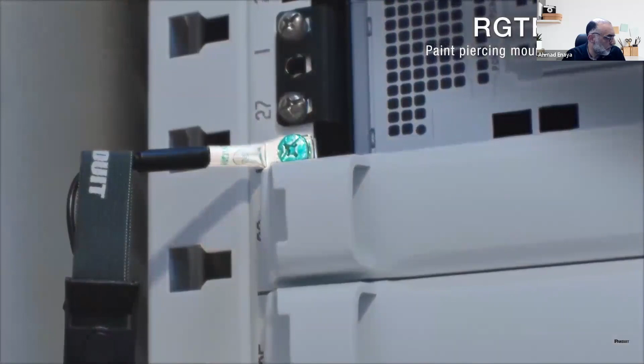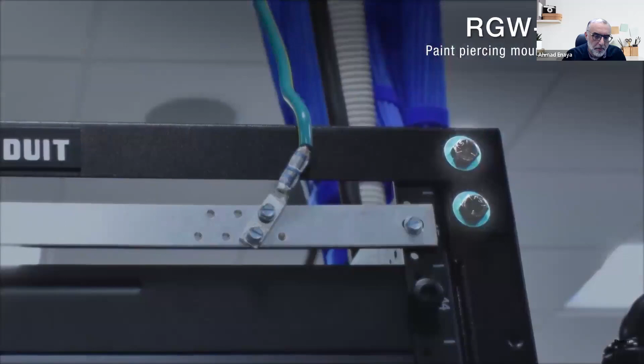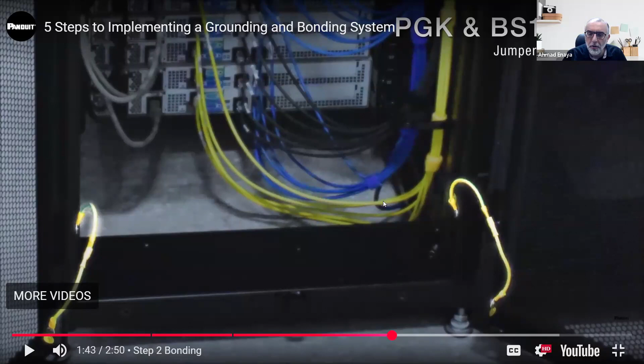Step 3 is to ensure that the cabinet or rack you are bonding to is electrically continuous. Even if there are signs of the frame being welded, you should always use paint-piercing hardware to bond sections together to reduce resistance. Make sure any separate panel or door hinge is also connected with a jumper. Even the rack door should be bonded, should be connected to the rack to make sure they are all at the same voltage level.